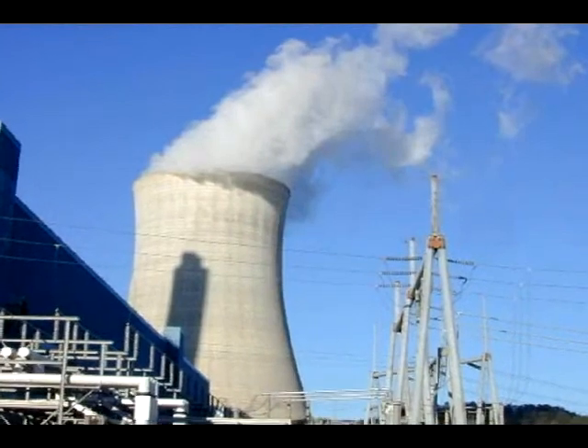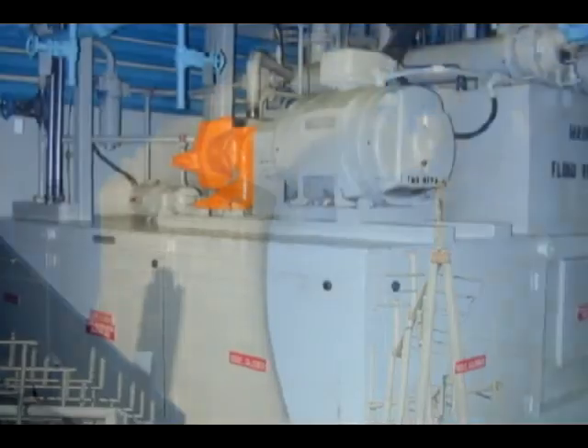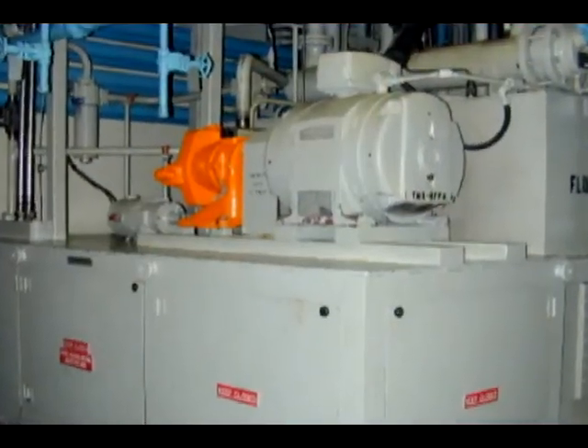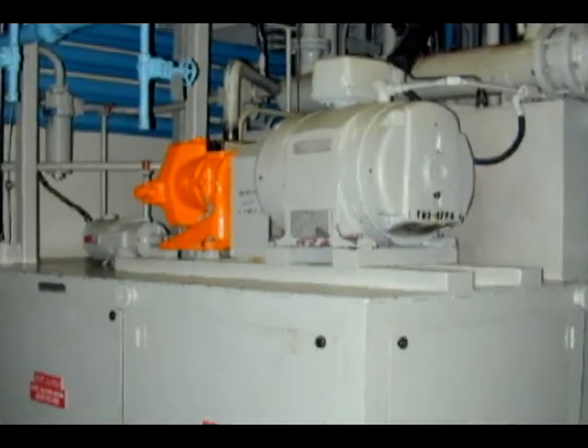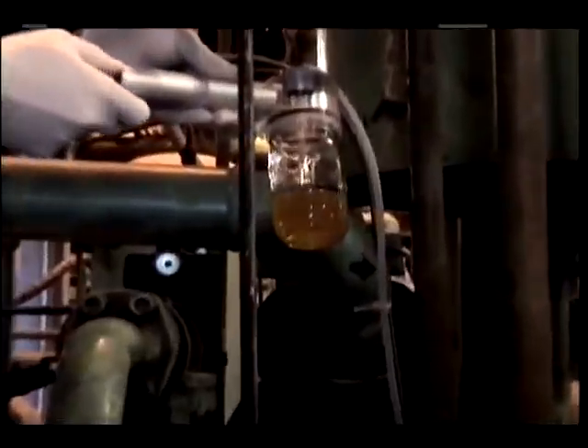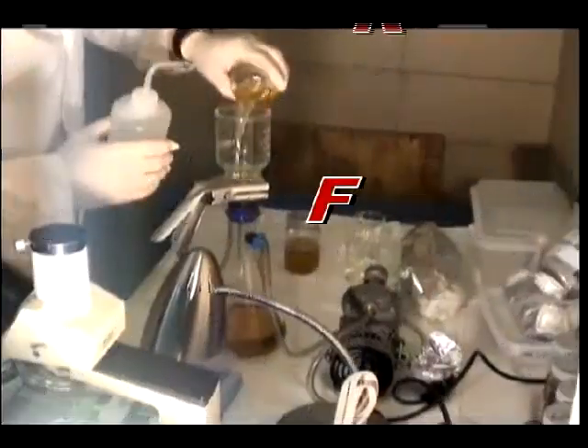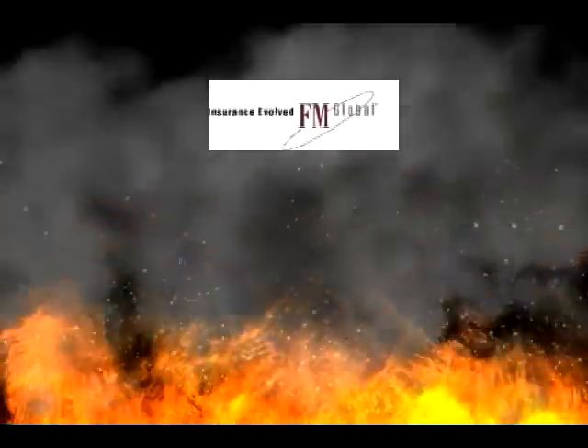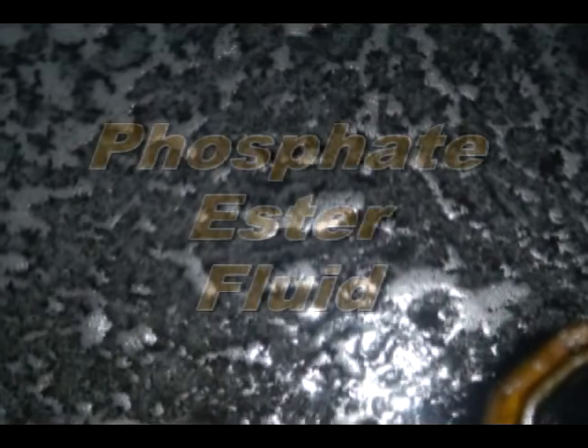For nearly 40 years, the electric utility industry has been using fire-resistant fluids in their turbine hydraulic fluid systems. These fire-resistant fluids, also referred to as FRFs, are required not only to reduce the possibility of a catastrophic fire resulting from a system leak, but insurance companies demand the use of FRFs on turbine hydraulic fluid systems. The predominant FRF that has been used in these systems is a phosphate ester fluid.